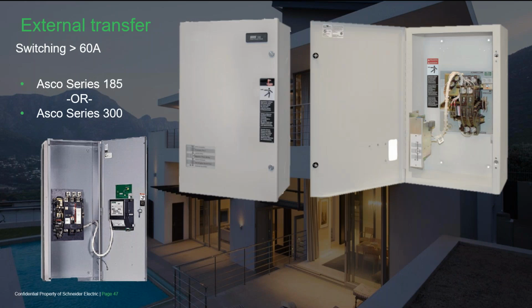Many customers choose the ASCO transfer switch because they are cost-effective and reliable. The fact that they are a Schneider Electric division is an added value. The Series 185 is the most basic model, but lacks programmability for specialized applications. When switching may need to be prioritized in a manner that is more complex, the Series 300 provides greater flexibility and can use a dry relay contact for external control commands. Other high-end transfer switches are also available from ASCO, such as the Series 7000. These are able to alternate between two different generators.